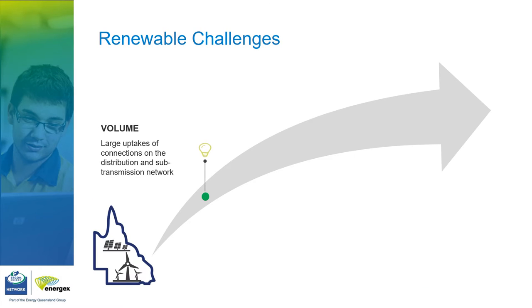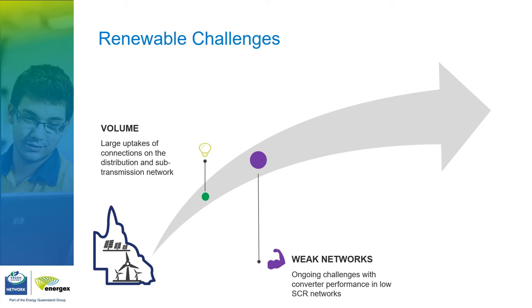So as I mentioned before, one of the biggest issues we have is the large uptakes of connections on the distribution and sub-transmission network. But we're also seeing other challenges as well, such as the impacts of weak networks and in particular the connection issues associated with low short circuit ratio networks. We're also seeing issues around the modeling aspects. Obviously, the progression of modeling has moved towards PSCAD and EMT level model requirements, which has placed a lot more requirements around what we need in terms of the assessment process.